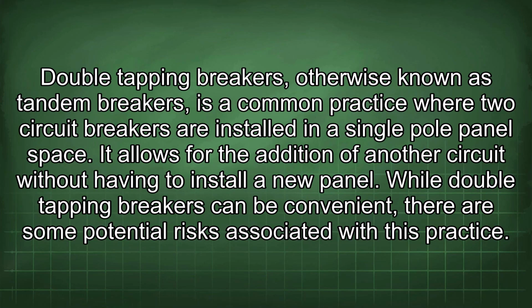Double tapping breakers, otherwise known as tandem breakers, is a common practice where two circuit breakers are installed in a single pole panel space. It allows for the addition of another circuit without having to install a new panel. While double tapping breakers can be convenient, there are some potential risks associated with this practice.